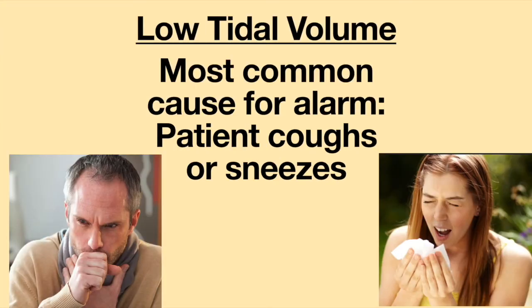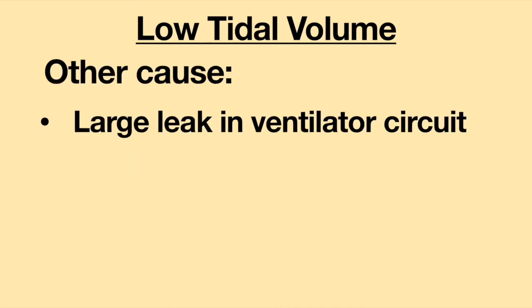A low tidal volume alarm frequently happens after a person coughs or sneezes. A low tidal volume alarm will also be triggered by a large leak in the ventilator circuit.